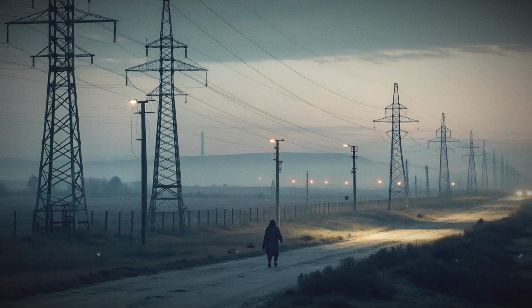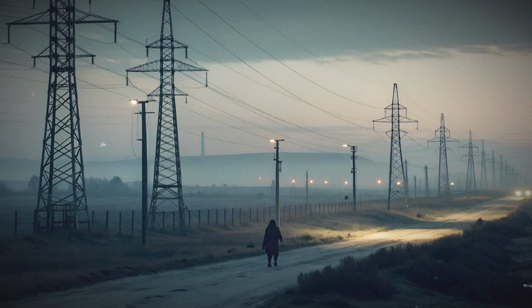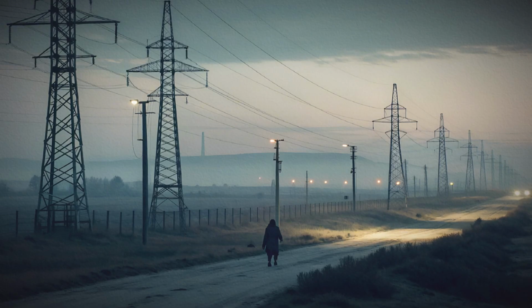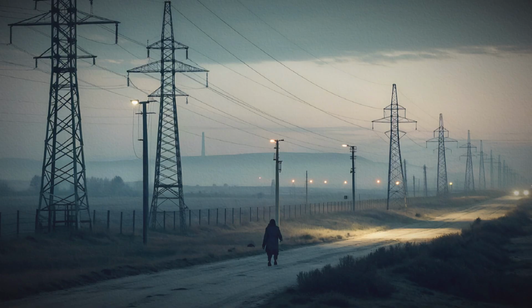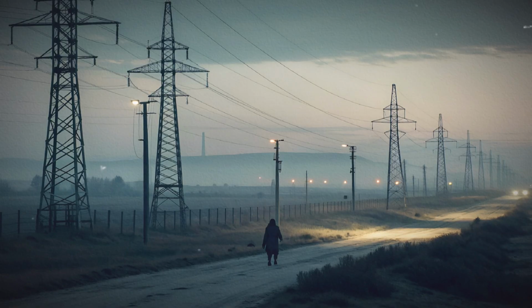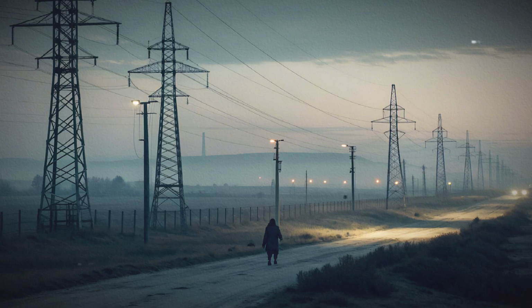In densely populated or constrained corridors, bundled conductors are common. Bundling places 2 or more conductors per phase. That arrangement reduces the electric field strength around each conductor and lowers losses due to corona discharge. It also improves the line's capacity to carry current.